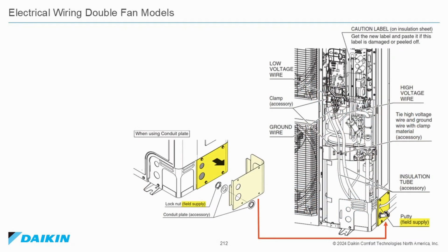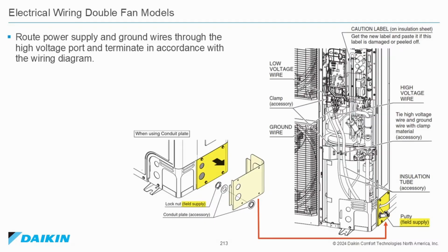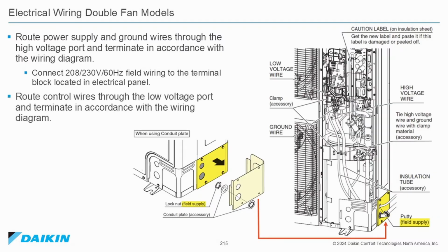Electrical wiring for double fan model units. Route the power supply and ground wires through the high voltage port and terminate in accordance with the wiring diagram. Connect 208 230 volt 60 Hz field wiring to the terminal block located in the electrical panel. Route control wires through the low voltage port and terminate in accordance with the wiring diagram.